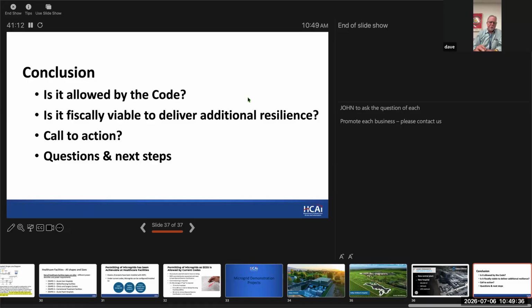One clarification, Jamie. I want to make sure I understand the technical aspects. The fuel cell is not seismically certified, so it's connected on the utility side of the ATSs, correct? Correct. So if it's going to operate when the grid is down to sustain the facility and keep the ATSs closed, how does it address the anti-islanding Rule 21 issues? It turns off, it disconnects. So there is a period of time, a few cycles, where there is no power. So they have, I guess, a relay.